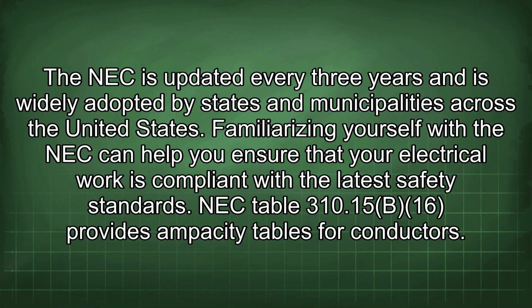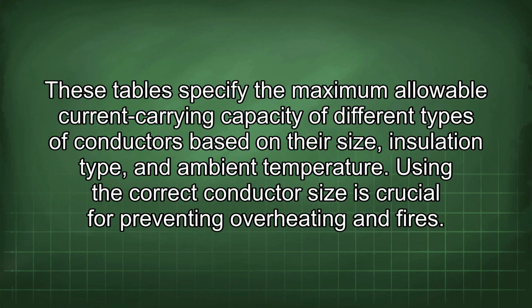NEC Table 310.15(B)(16) provides ampacity tables for conductors. These tables specify the maximum allowable current carrying capacity of different types of conductors based on their size, insulation type, and ambient temperature. Using the correct conductor size is crucial for preventing overheating and fires.